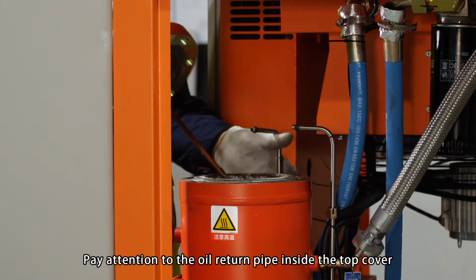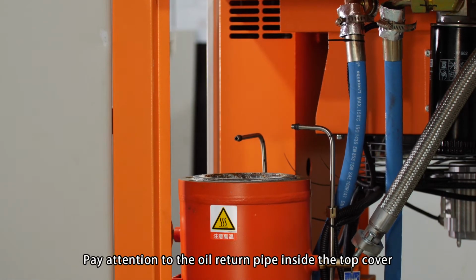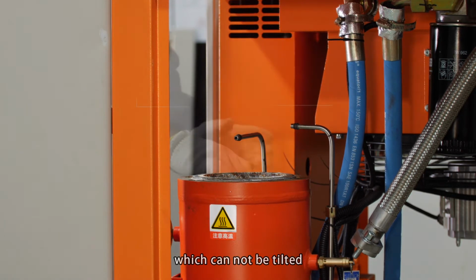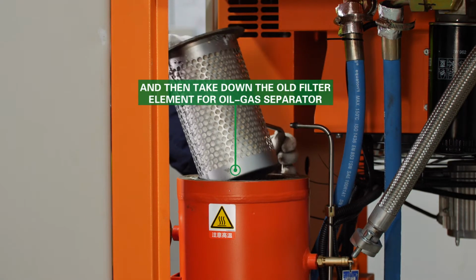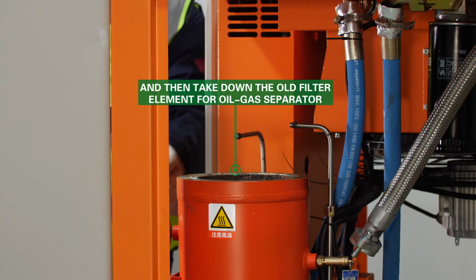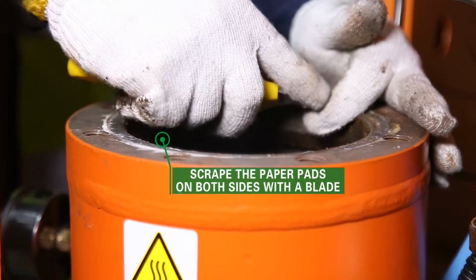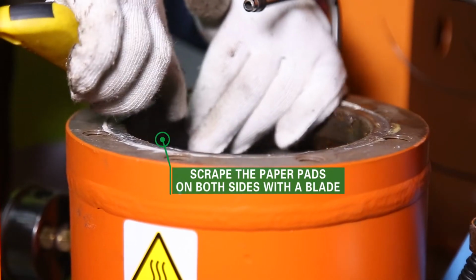Pay attention to the oil return pipe inside the top cover, which cannot be tilted, and then take down the old filter element for oil-gas separator. Finally, scrape the paper pads on both sides with a blade.